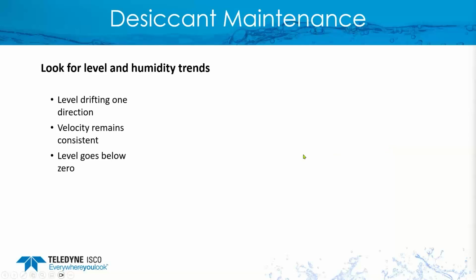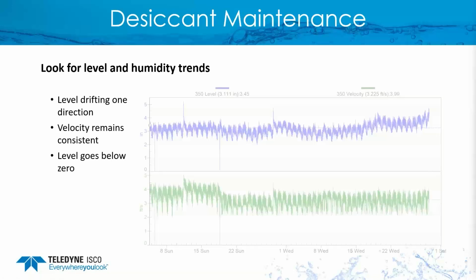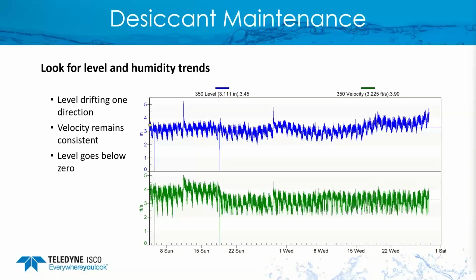Now, what I like to look at is the trends that I had mentioned. Some of the things that you may find is that the level can actually drift. So if you have a pressure transducer, one thing you would look for is, see if the level remains constant, follows the same diurnal pattern that you're used to, or you may find that your velocity remains consistent, or even that the level goes below zero.